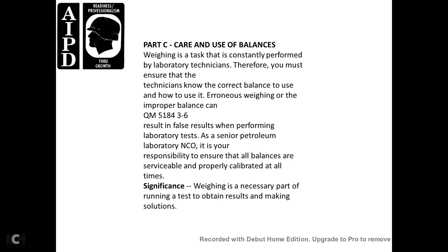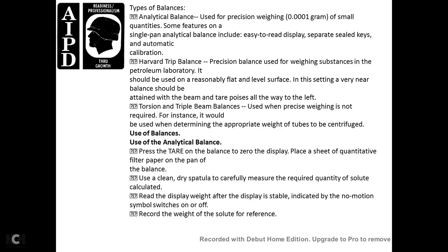Care and Use of Balances. Since weighing is constantly performed in the laboratory, technicians must know how to correctly balance and use balances. Erroneous weights from improper balance use will produce faulty results. The senior petroleum laboratory NCO is responsible for ensuring all balances are serviceable and properly calibrated at all times. Types of balances: the analytical balance is used for precision weighing to one ten-thousandth (1/10,000) of a gram for small quantities. Features of single-pan analytical balances include an easy-to-read display, separate sealed keys, and automatic calibration.